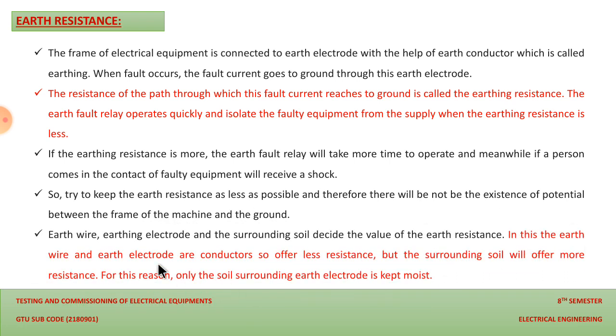So the earth wire or earthing electrode and the surrounding soil decide the value of earth resistance. If the soil is dry, then the resistance of that soil is more, and if the soil is moist or has more water, as I have already discussed, then the resistance of the soil is less. In this, the earth wire and earth electrode are conductors, which offer less resistance, but the surrounding soil will offer more resistance, because as we move away from the earth electrode, the resistance of the soil will increase, or we can say potential will decrease.